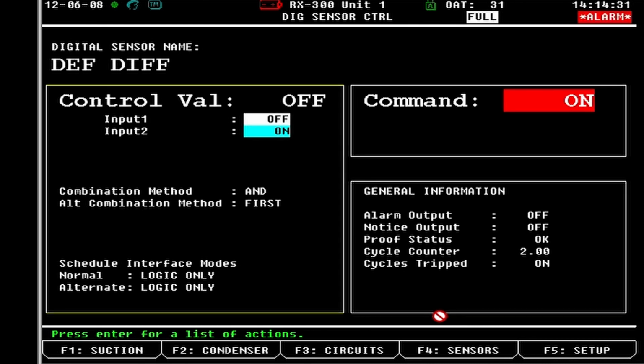See, control value turned to off, and the command's going to also switch off here in a second. So we have it set up for pulsing still, so as soon as it pulses off, see, it turned off. As soon as the pulse turns off. But that is a digital sensor control. Like I said, this is one common thing for it.